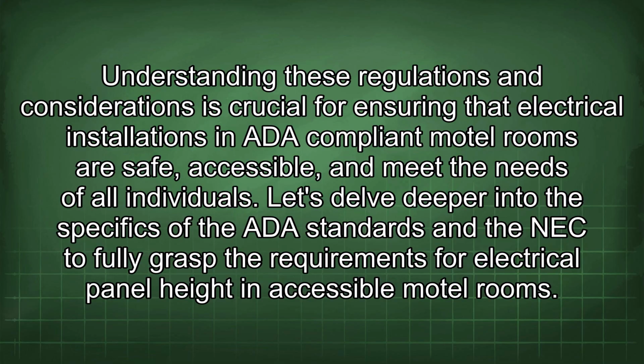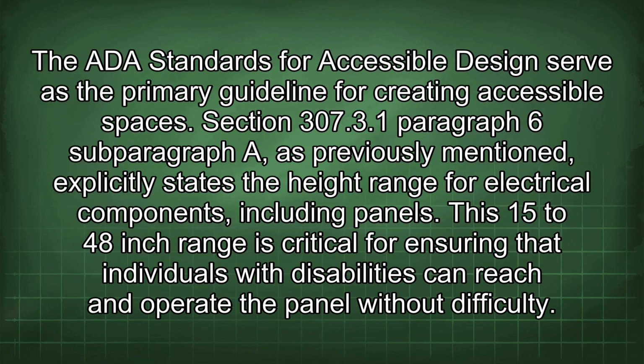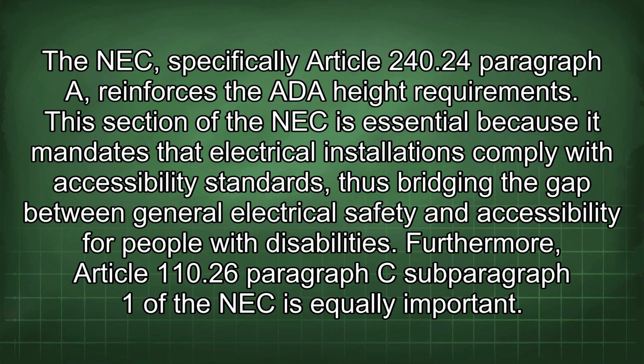Let's delve deeper into the specifics of the ADA standards and the NEC to fully grasp the requirements for electrical panel height in accessible motel rooms. The ADA standards for accessible design serve as the primary guideline for creating accessible spaces. Section 307.3.1 paragraph 6 subparagraph A, as previously mentioned, explicitly states the height range for electrical components, including panels. This 15 to 48 inch range is critical for ensuring that individuals with disabilities can reach and operate the panel without difficulty. The NEC, specifically Article 240.24 paragraph A, reinforces the ADA height requirements. This section of the NEC is essential because it mandates that electrical installations comply with accessibility standards, thus bridging the gap between general electrical safety and accessibility for people with disabilities.